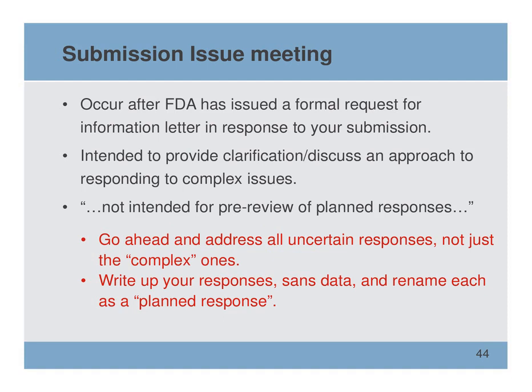Submission issue meetings. Right, so FDA says it's not intended to pre-review planned responses. So, yeah, that's true, but what we've done a lot of times is said, okay, you've asked us 7 questions. Here are our planned responses, essentially our draft responses for all 7 questions. And the first question may be one where we simply say, yes, we will give you that information. Now, there may be more testing needs to be done, but we're just going to say, yes, we're going to give you the information, because now we're giving them a sense of, hey, we're on the same page. We have some disagreements, but there are some things we agree with.